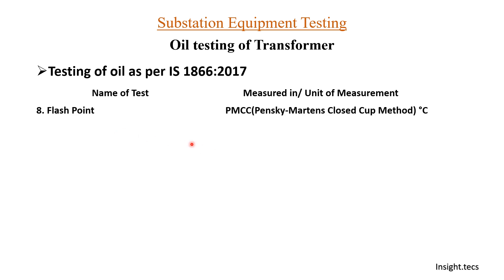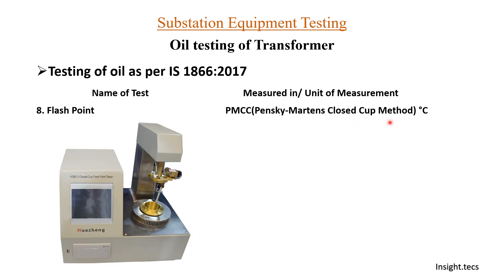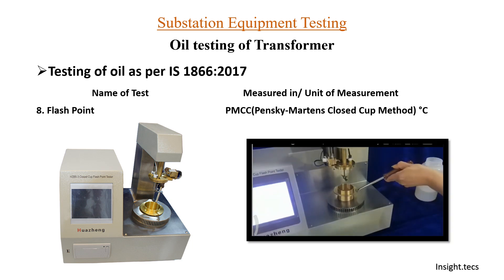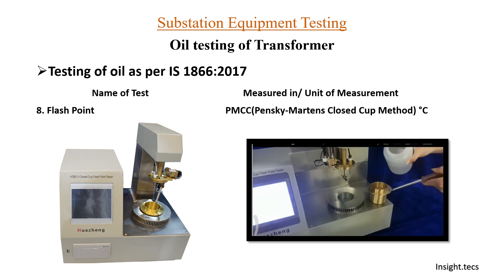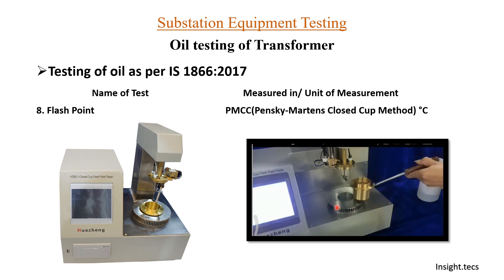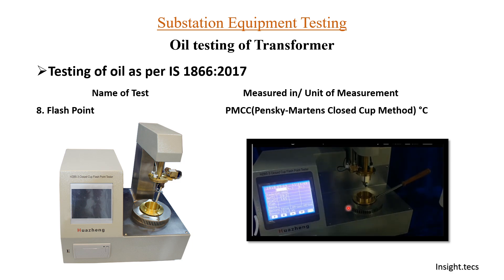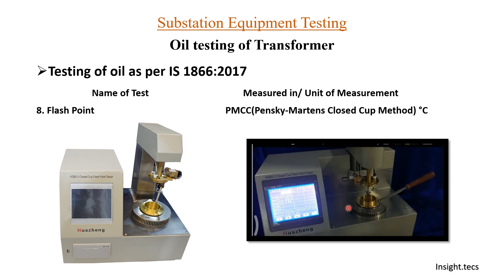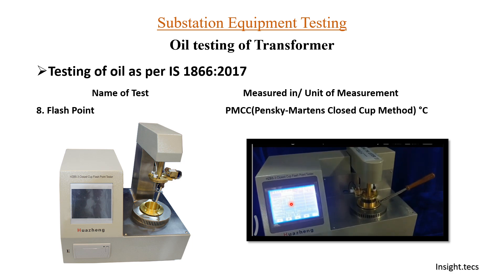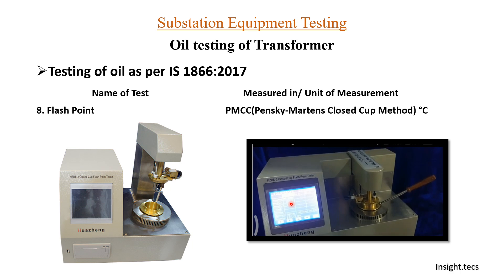Next is the flashpoint. It is also called the Pensky-Martens closed cup method. This is the test device — this is the cup, and in this we will take the sample oil as you can see. We will place the cup back into the equipment and enter all the required parameters. All the input required about the oil sample is already provided, and now we will start the test.